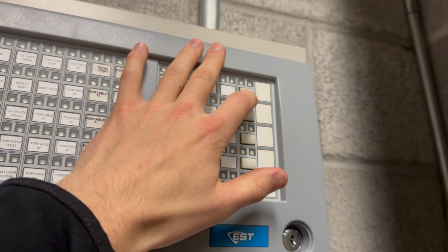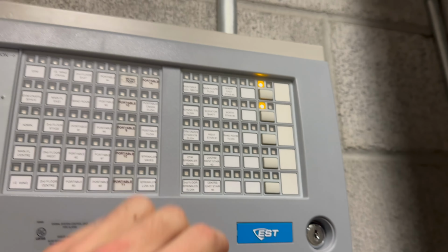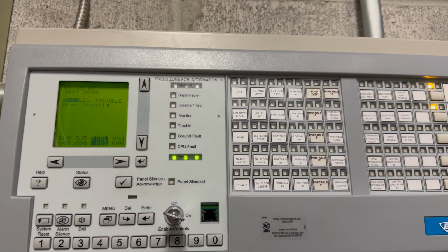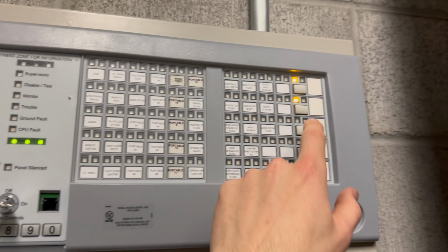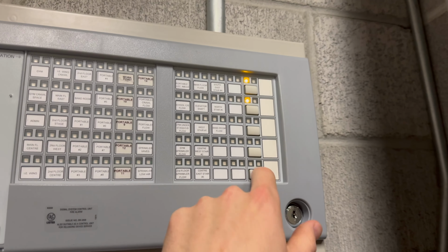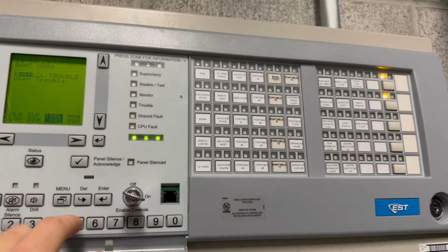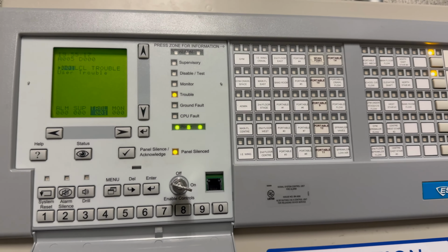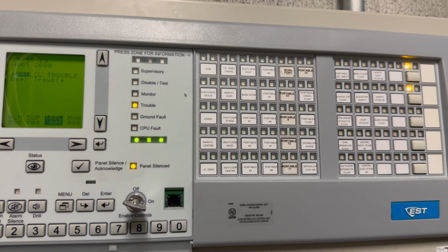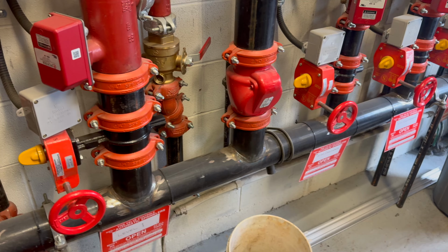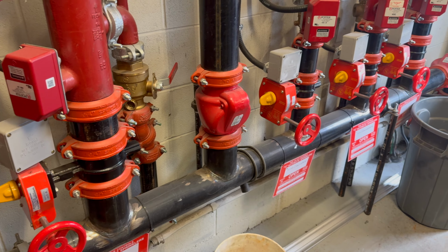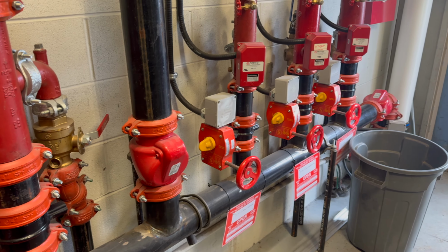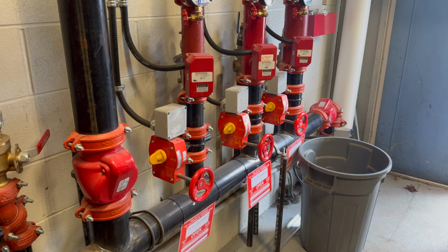And we're going to, what time do you have? I just want to see we're on the same time zone. Might get a trouble signal. There is our disables. They're not labeled, unfortunately, but they are relay and bell disable. Yeah, you should have had a trouble. Trouble would have been at 10:08. We can give a supervisory in a couple of minutes.